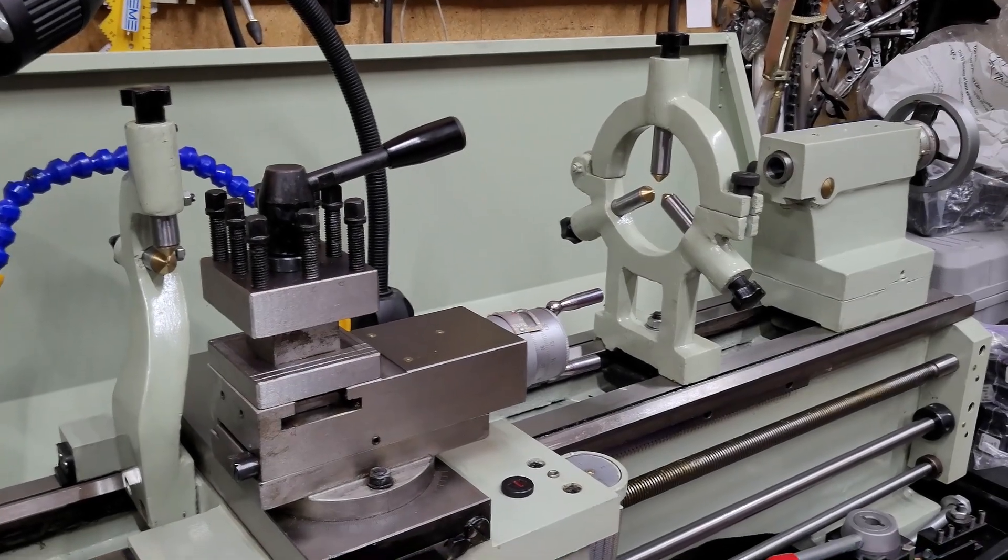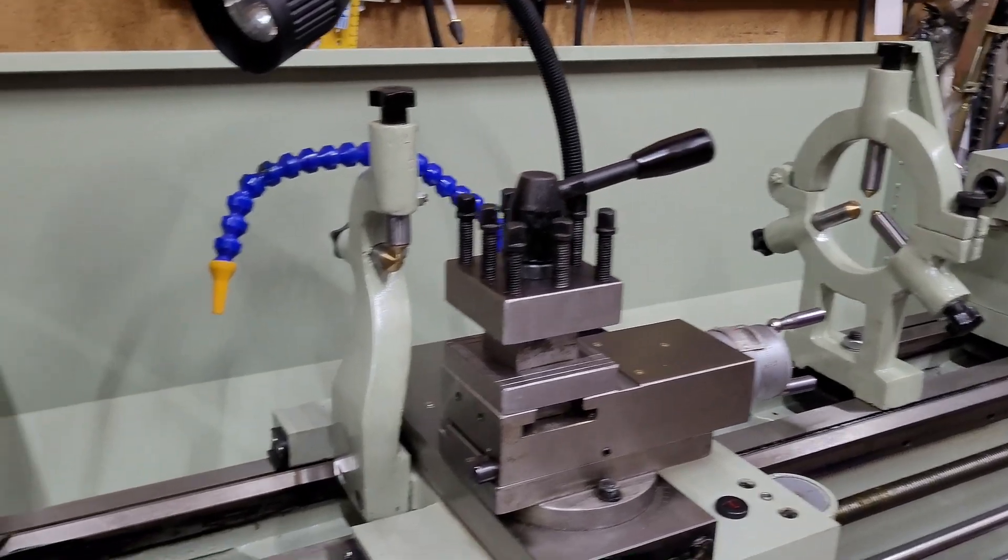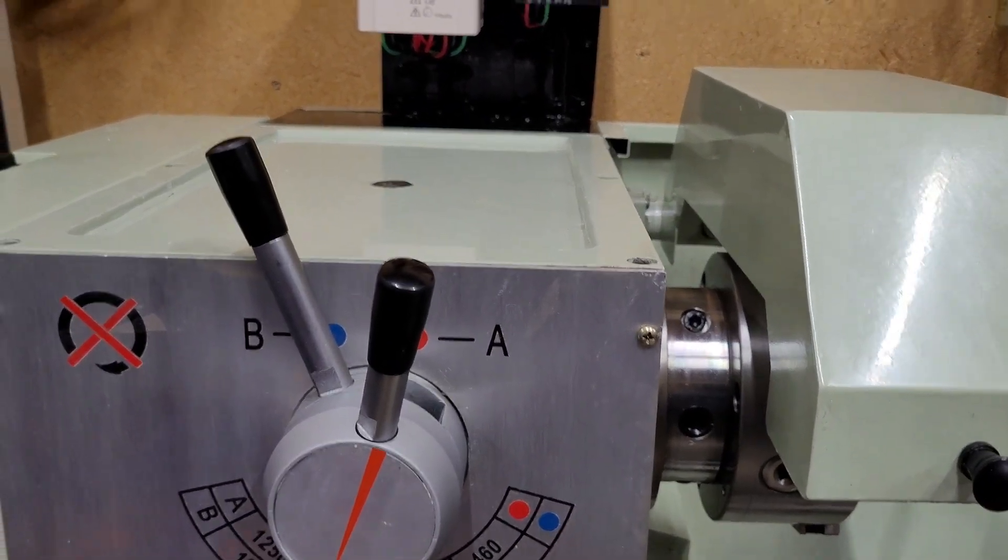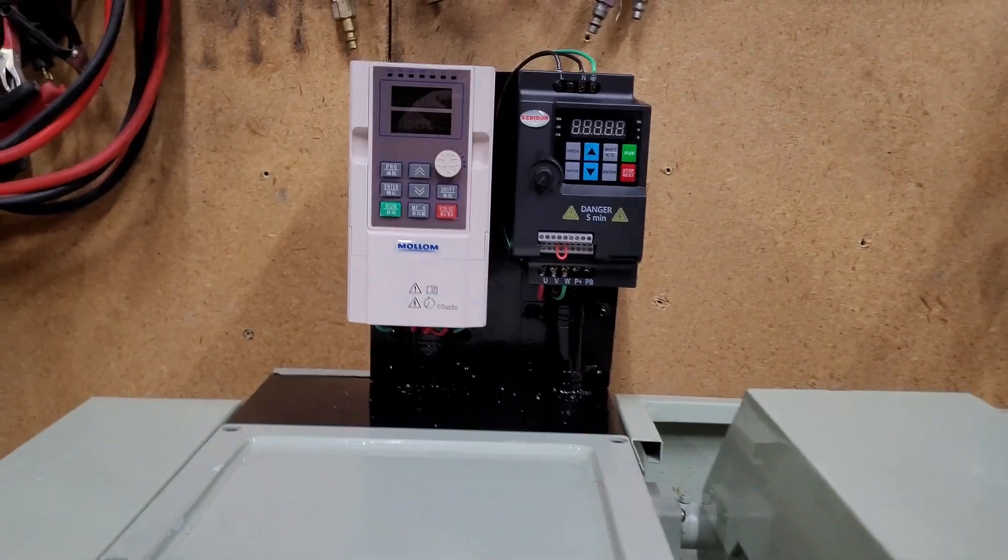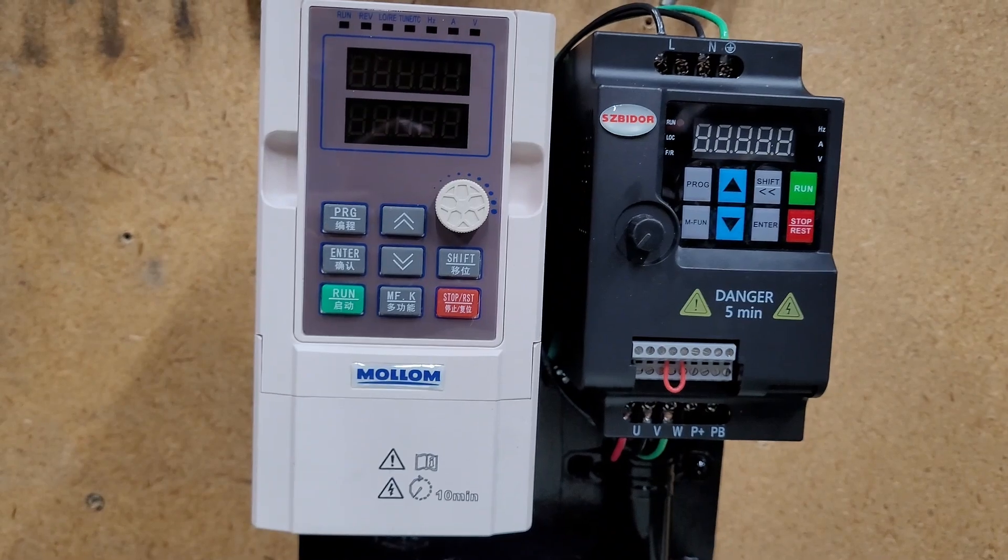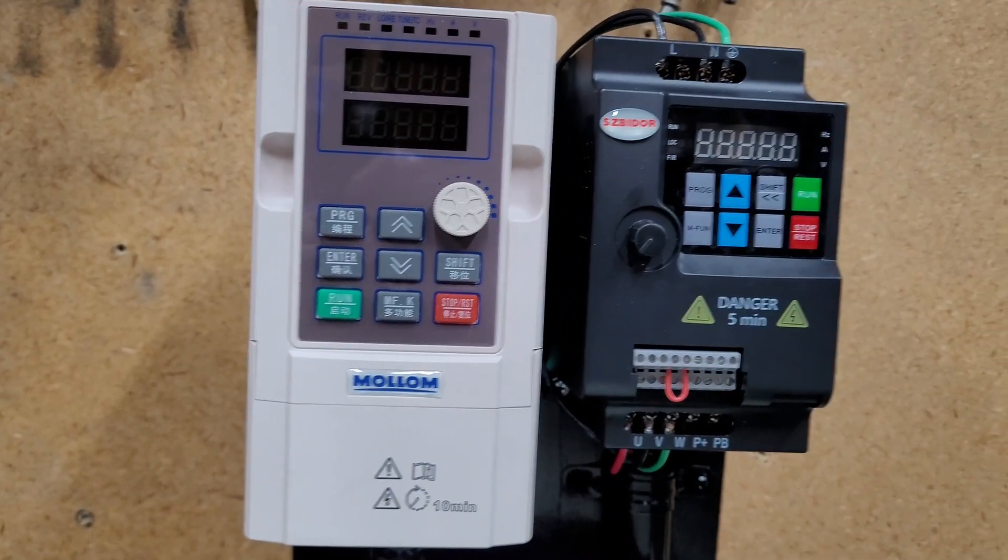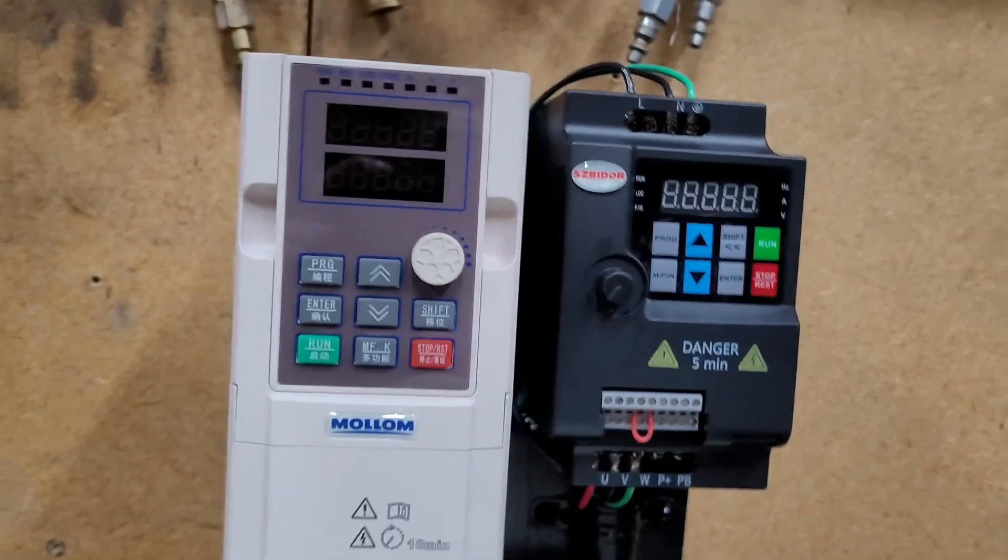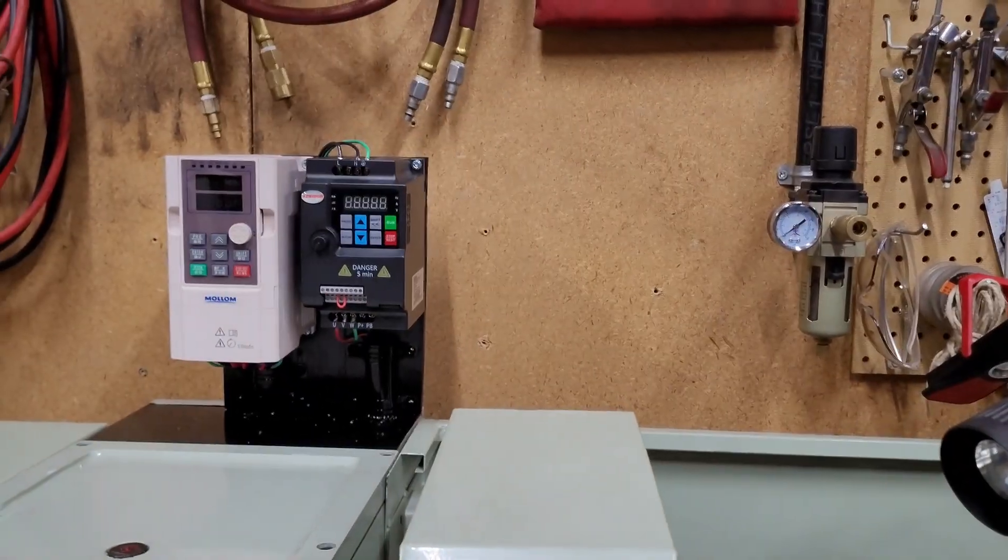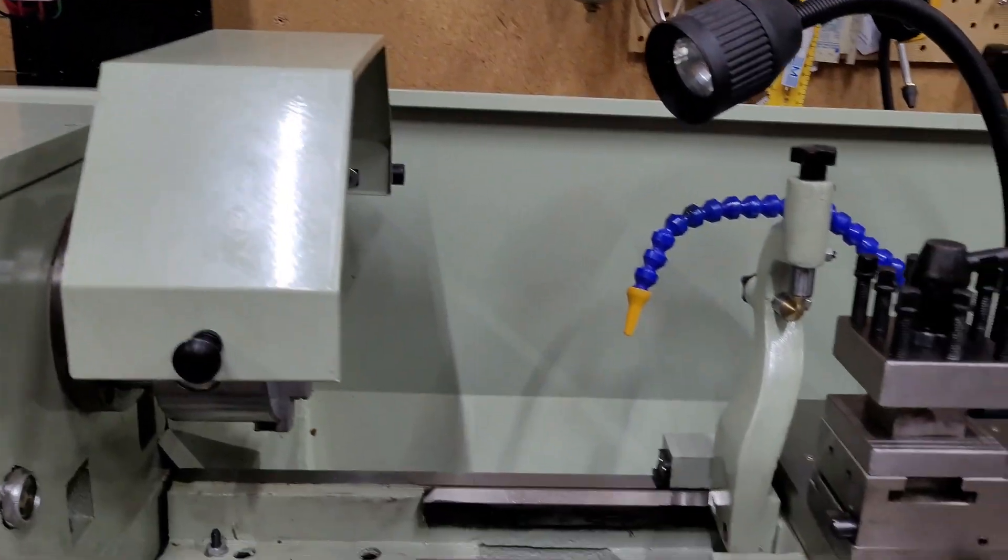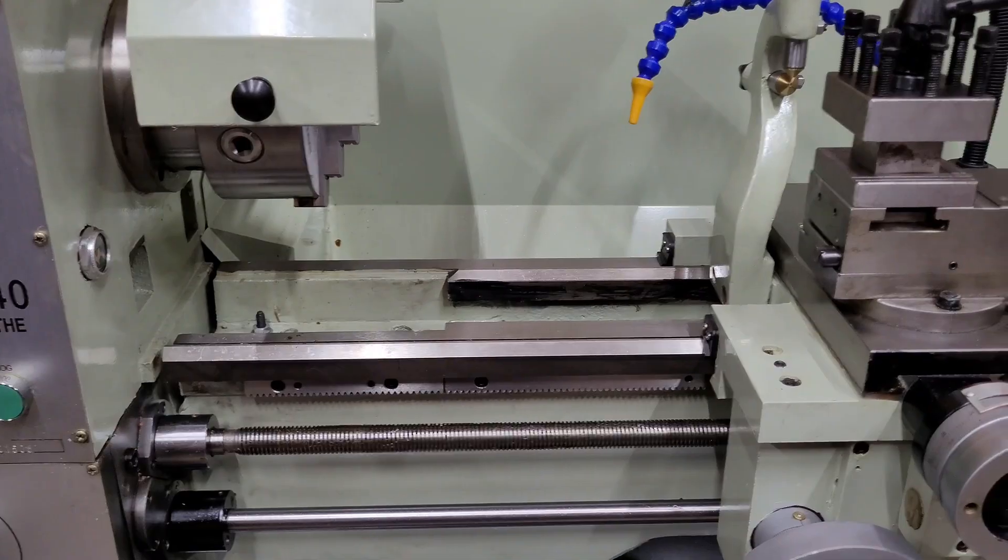In today's video, I'm going to show you how to convert a three-phase lathe to a single-phase lathe, so you can run it off residential 240. The motor is going to remain three-phase, run by the VFD on the left, and the VFD on the right is for the coolant motor only. I'll show you how to wire it, how to program the VFDs, and make it compatible for residential use.